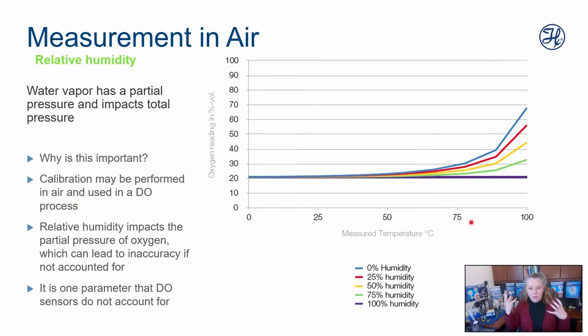And we're measuring in dissolved liquid. So if you calibrate in dry air, you're failing to take into account the contribution of humidity in the solubility of oxygen. Remember, it's a partial pressure measurement. So you need to understand the effect of humidity on your calibration, because that will impact how you do your calibration, which will ultimately impact how accurate your final measurement is. Okay. And I'll show you a little bit more about that later as well. But this curve just gives you some ideas about how the warmer you get, the humidity has a significant impact on solubility.